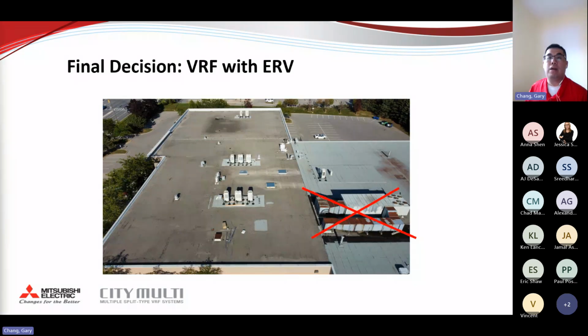So you can see here, our final decision was a VRF with ERV, because refrigerant piping also needs to be insulated. And you can see we are placing the VRF system closer to the zone that it is serving. So that will reduce the amount of piping as well as the amount of ductwork associated with running along ductwork as well as refrigerant piping. And we're just having different ERVs taking outside air and providing it indoors. So we're going to go into a little bit more detail on that solution.